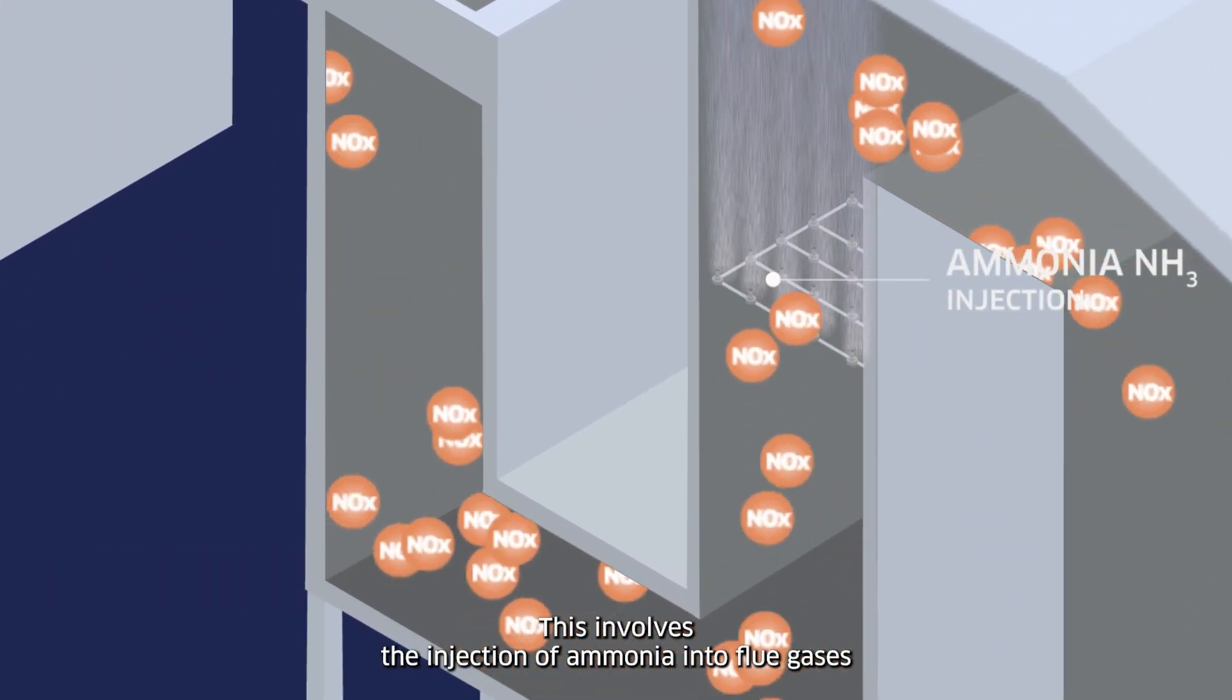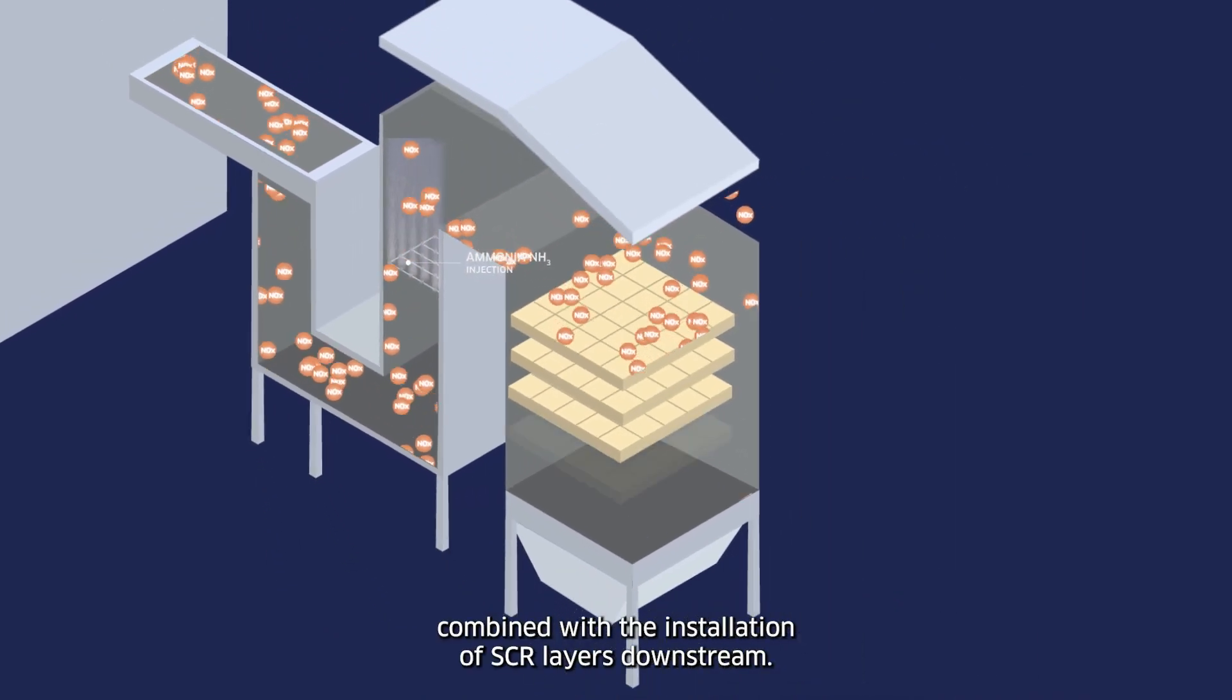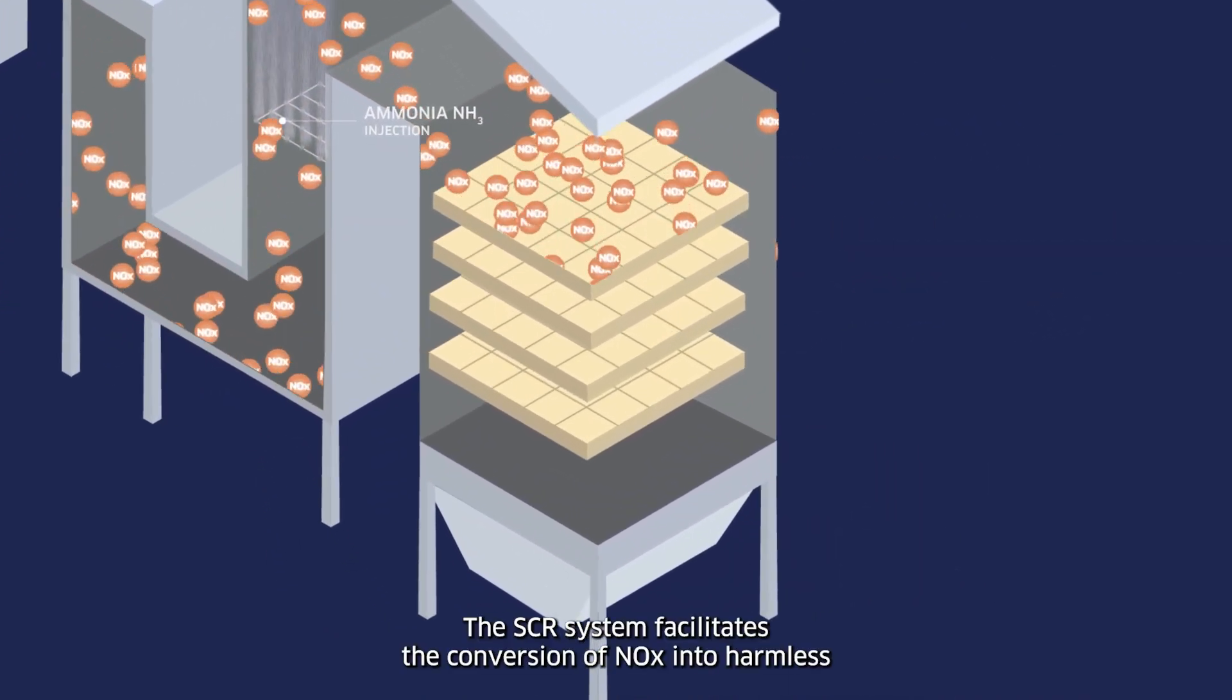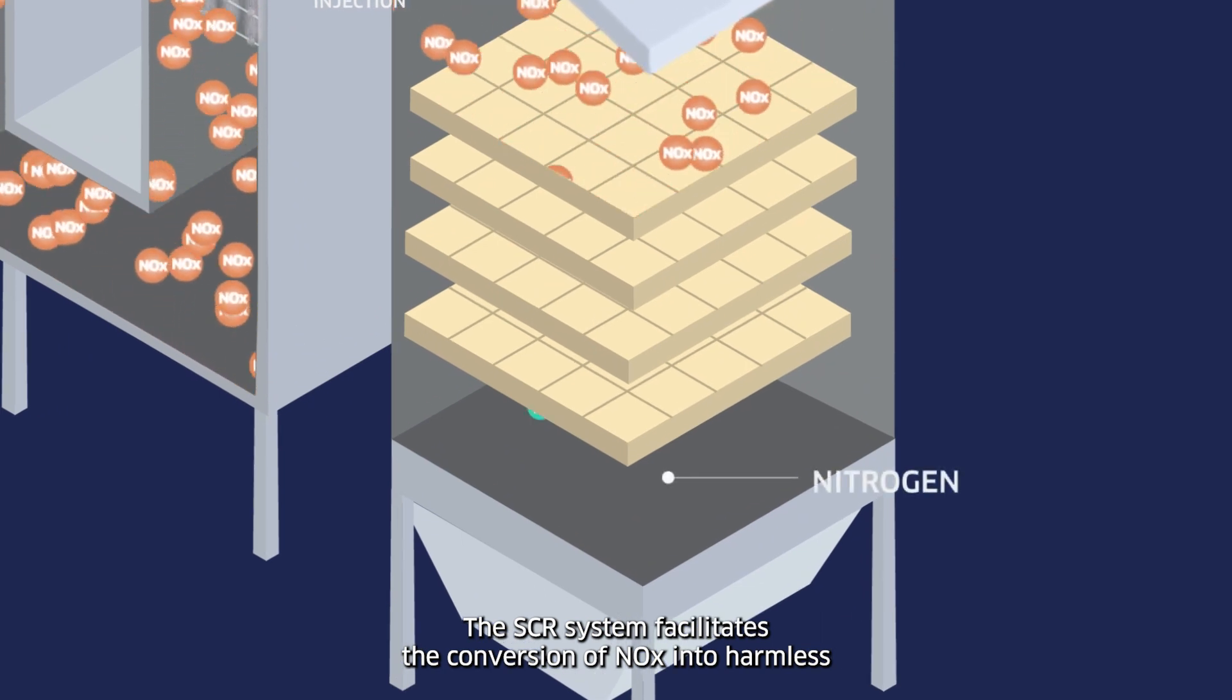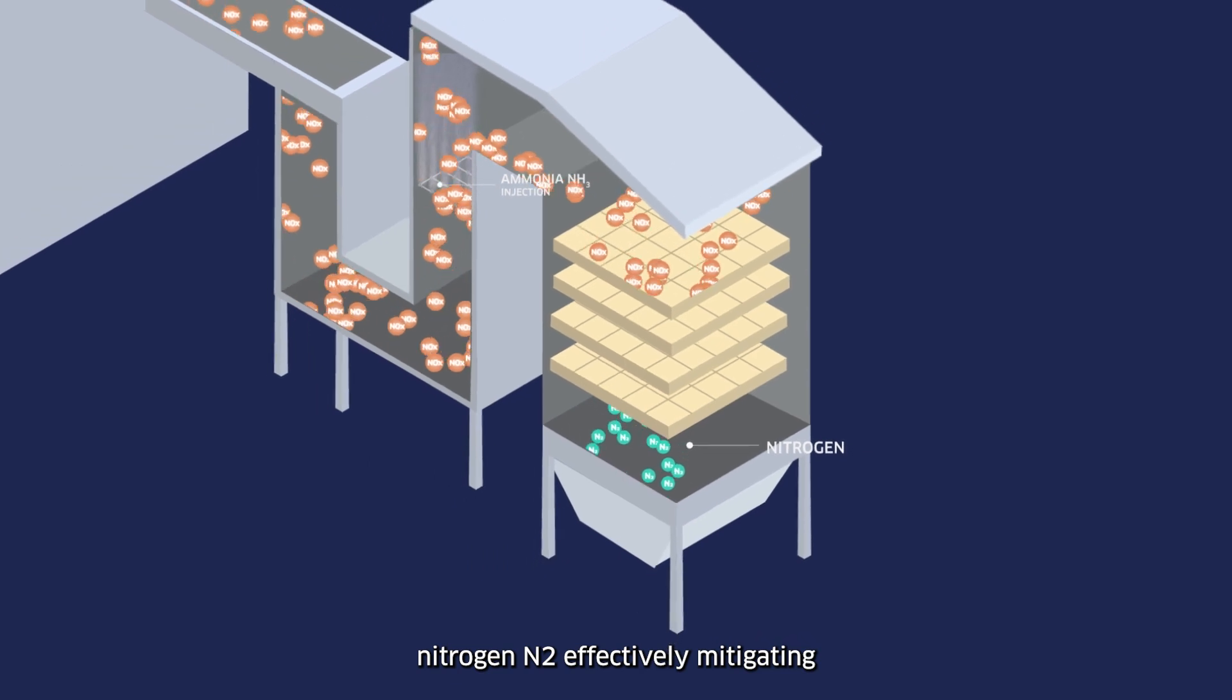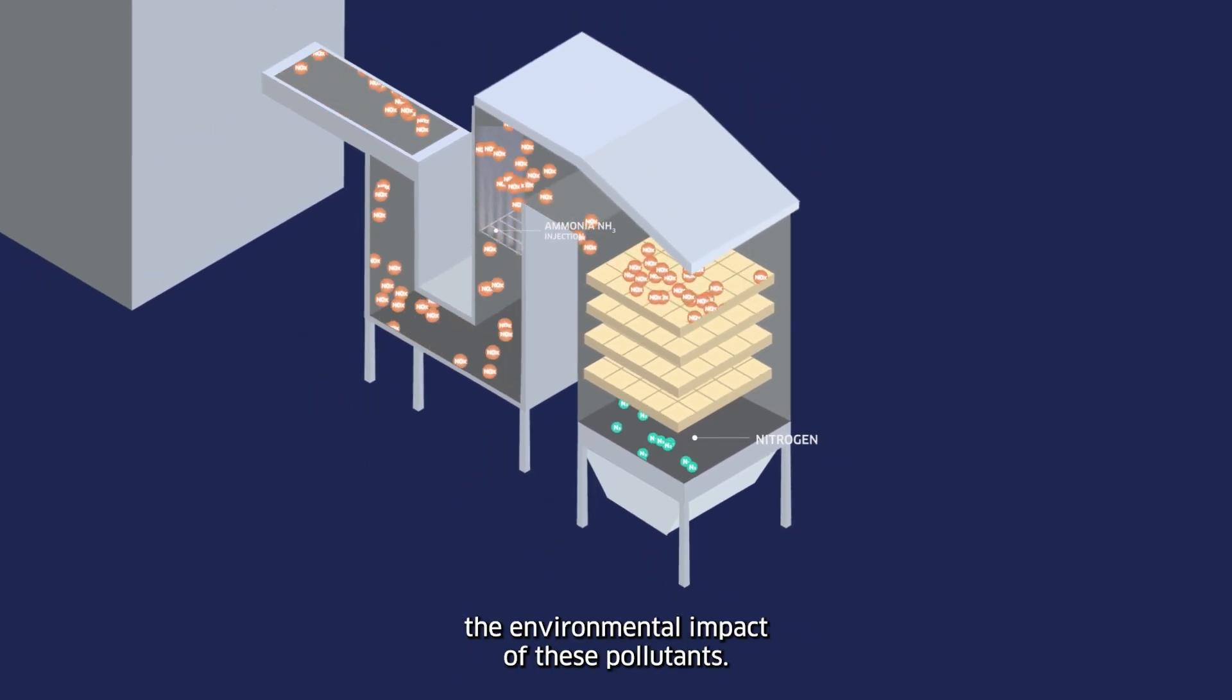This involves the injection of ammonia into flue gases, combined with the installation of SCR layers downstream. The SCR system facilitates the conversion of NOx into harmless nitrogen, N2, effectively mitigating the environmental impact of these pollutants.